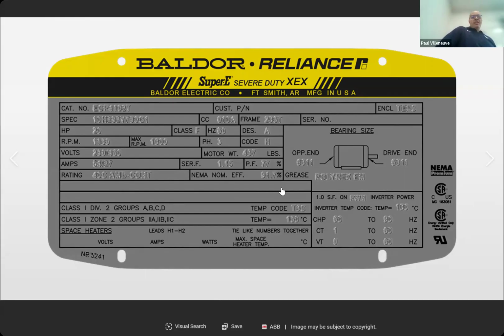You think about it, this is not even a premium efficiency. It's a severe duty, but we can get 94, 95 pretty easily. And then this one has nothing to do with the motor, other than the fact that, anybody know what Class 1 Div 2 means? It's in the National Electric Code. It has to do with hazardous area if it's flammable materials. You have a classification and a division. So it tells you the type of equipment that you are required to operate in there.